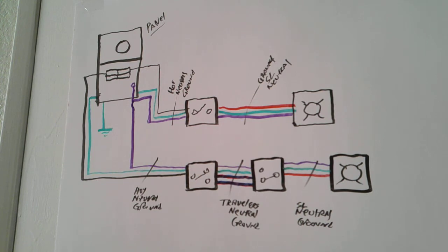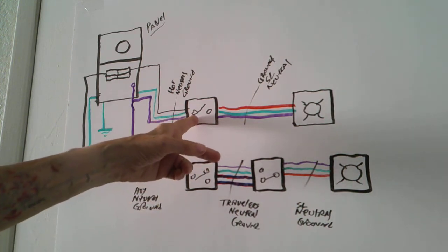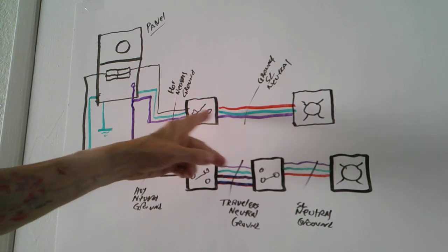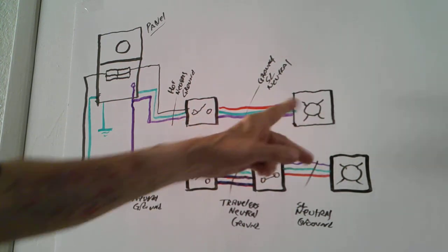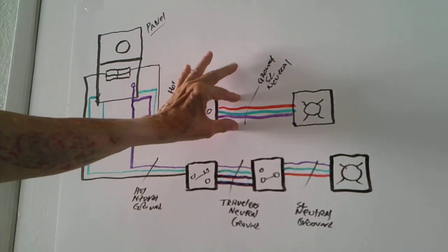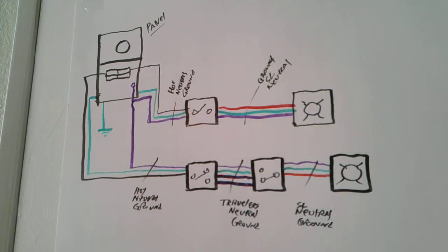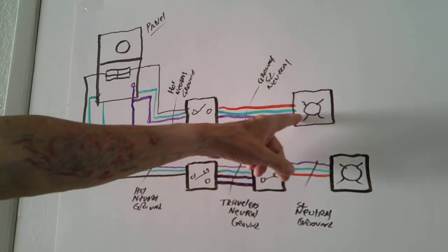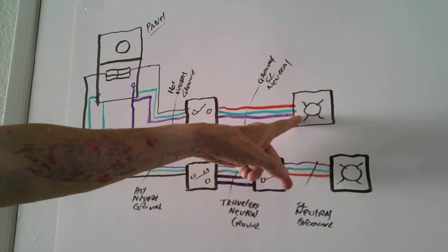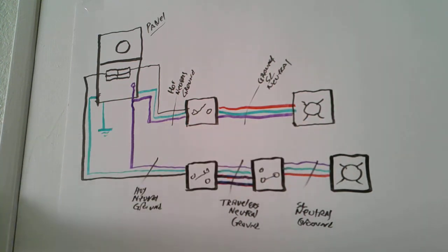Okay? Now, if you have power going to this switch and you don't have power going to this light, then what you want to do is check this group of wires. Quite possibly when you strip the wire, you nicked or broke or cut one of the wires. Now, if you have power going to this light fixture, then there's a good chance that the light fixture is bad. Okay? So that kind of gives you how you troubleshoot an electrical circuit.